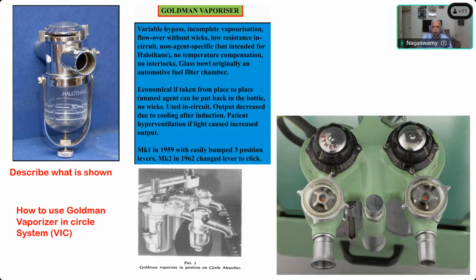And this is just for you to see, of historical interest. You can see there is an ether vaporizer attached, which is also included in the breathing circuit. This is a circle system with inspiratory and expiratory limbs. This is a pop-off valve. The ether canister is there, which is in off position. And you can see the soda lime also has a dial. So you can switch off the soda lime and use it only when required.